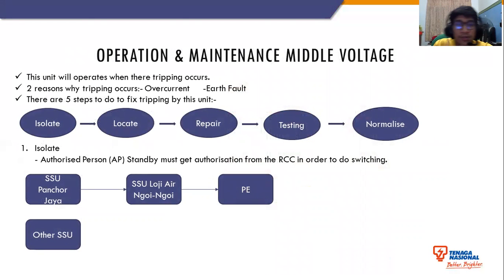Next, I will move on to the operation and maintenance for medium voltage. This unit will operate when tripping occurs. There are 2 reasons why tripping occurs. The first one is overcurrent and the second is earth fault. There are 5 steps to fix tripping by this unit. The first one is isolate. Then locate, repair, testing, and normalize.